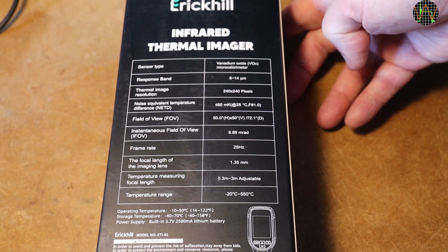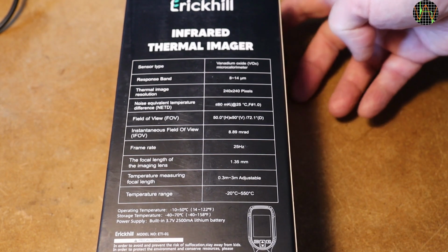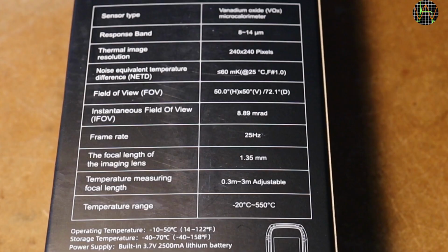With that out of the way, here's the quick list of specs. Imagine you are new to IR cameras, studying the specs of a camera, so maybe a quick assessment of what this says may be useful for you. The thermal resolution is 240 by 240 pixels, which is pretty good for a thermal imaging camera. Not long ago, such resolutions were only available on high-end cameras. On the other hand, the noise equivalent temperature difference, or NETD, of lower or equal 60 millikelvin is no more than middle of the road, meaning the sensitivity for small temperature differences could be better.